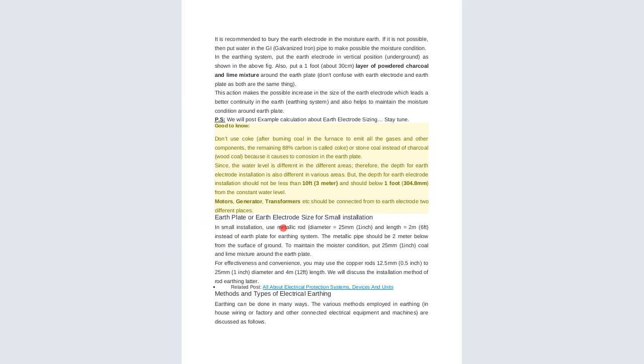Also, the earth plate and earth electrode size in a small installation. A small installation has metallic rods with a diameter of 25 millimeters, 1 inch, and a length of 2 meters, that is 6 feet, instead of the earth plate of the earthing system. The metallic pipe should be 2 meters below the surface of the ground to maintain the moisture condition. We have said that the moisture condition is a very important part.